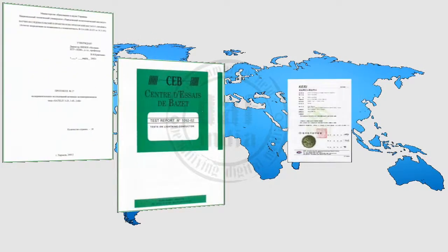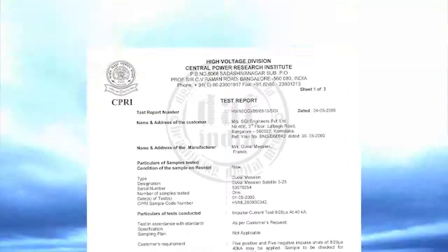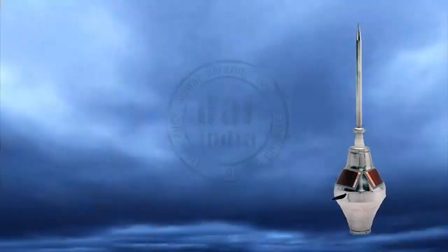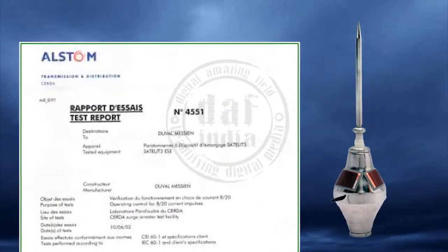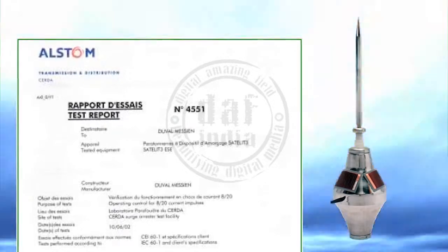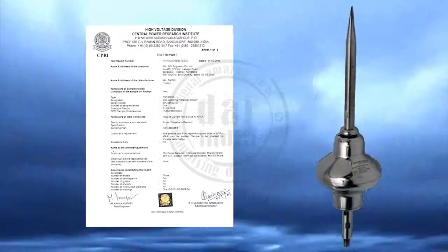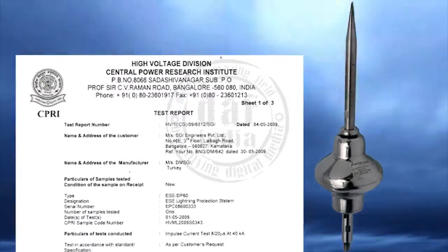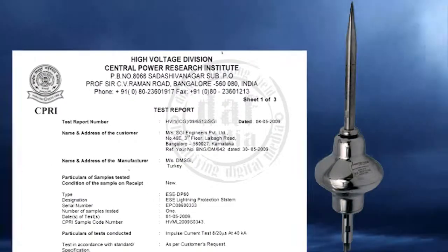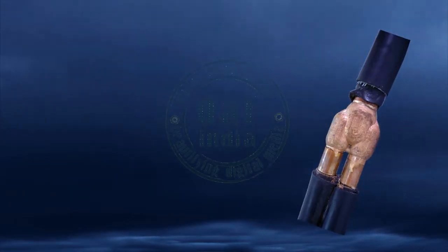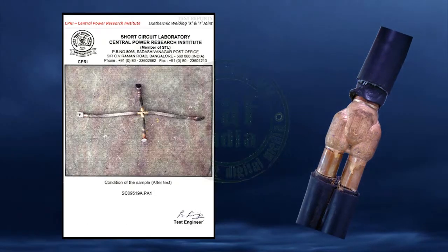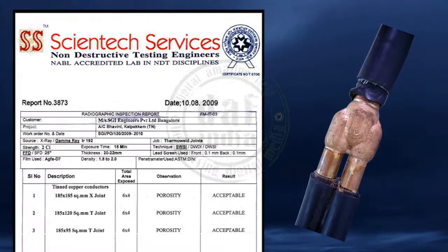Tested around the globe, Satelit 3 has made its mark in India. In CPRI, Satelit 3 is also tested up to 100,000 amperes in Alstom, Cerda. The Protector is tested in CPRI for positive and negative surges, and the thermoweld joints are tested in CPRI as per IEC 837.